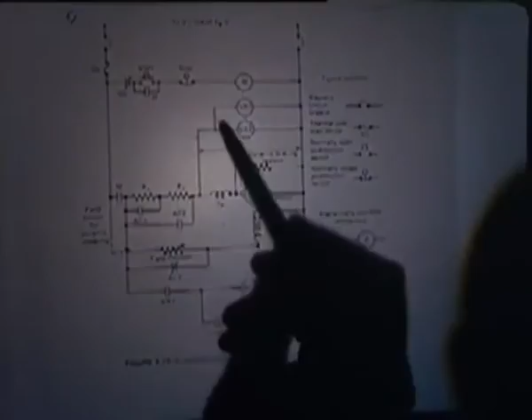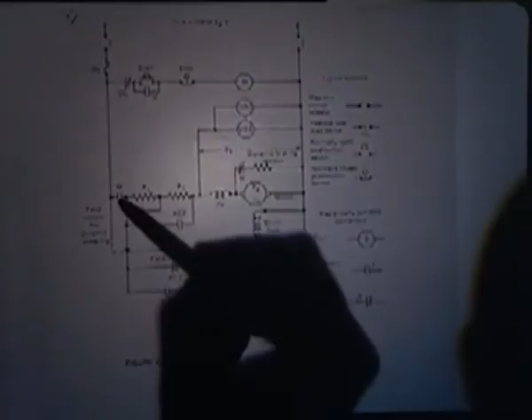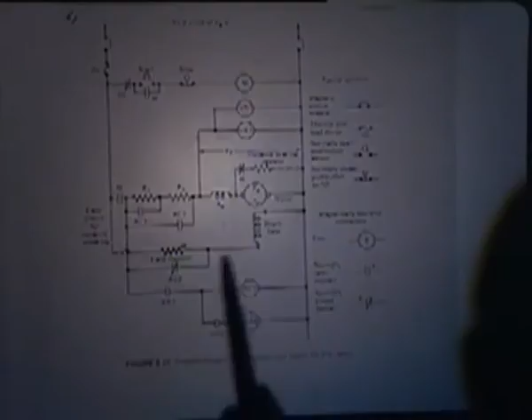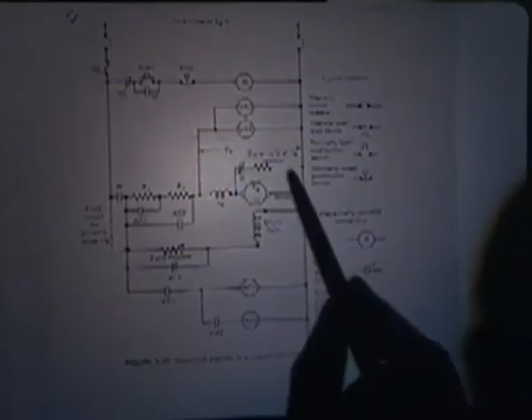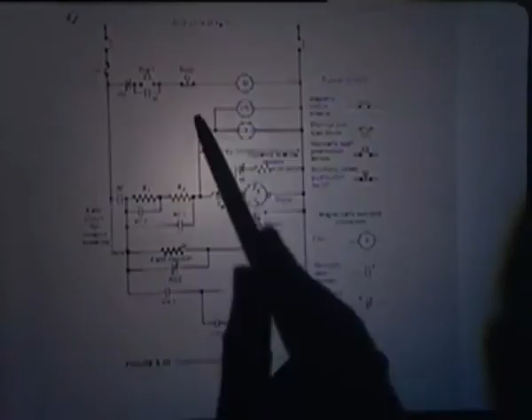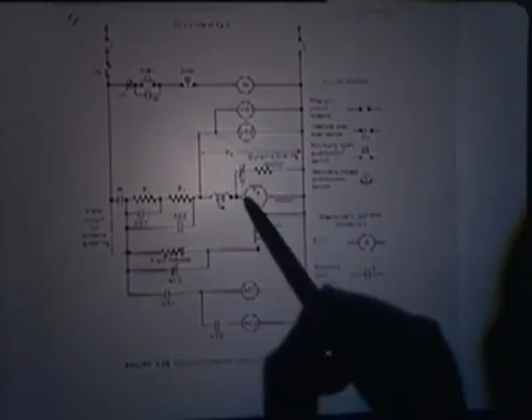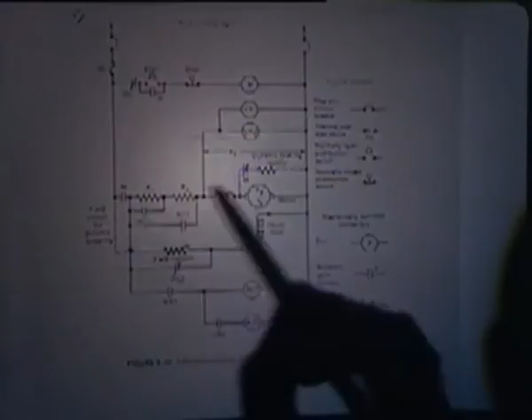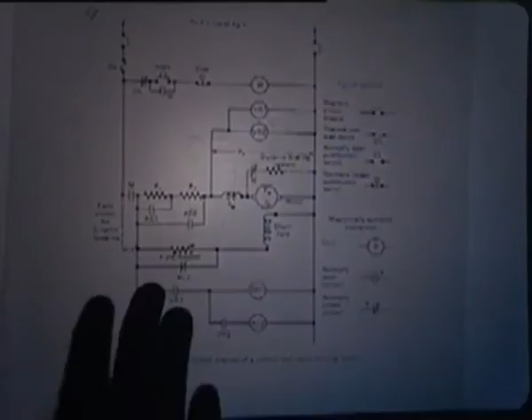Similarly, if you want to stop the machine, all you have to do is push the stop push button, and then M gets de-energized, this contactor opens and this one opens, and the motor is disconnected from the supply. But there is an additional feature of braking. If you want to quickly stop the machine, you can also put in a braking resistor. That is the dynamic braking resistor. When you want to stop it, this M gets energized and this resistor comes into the picture, this gets opened, and it quickly comes to a stop. These are the features of an automatic starter.